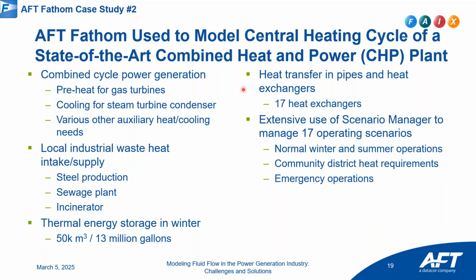They also used heat transfer modeling in our software, which I mentioned earlier—a lot of pipe flow modeling tools can't actually do heat transfer and the thermal balance on their system, but Fathom can. I've been doing that for almost 30 years, and they made extensive use of it with heat transfer in the pipes and the heat exchangers—17 heat exchangers—where heat went in and out, and they did a complete thermal balance on the system.